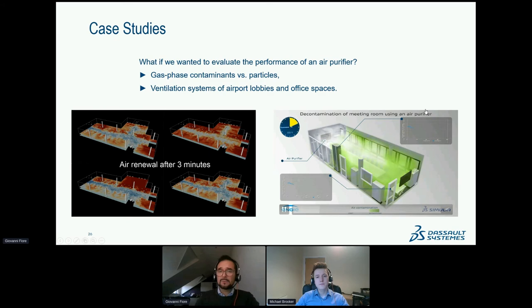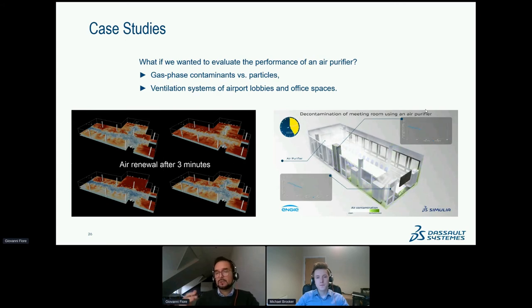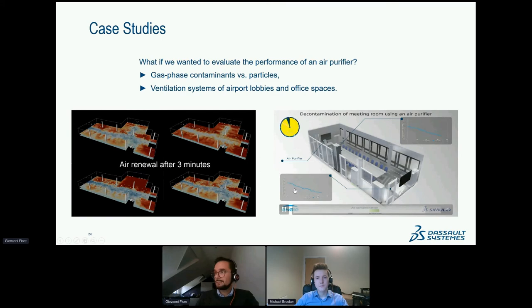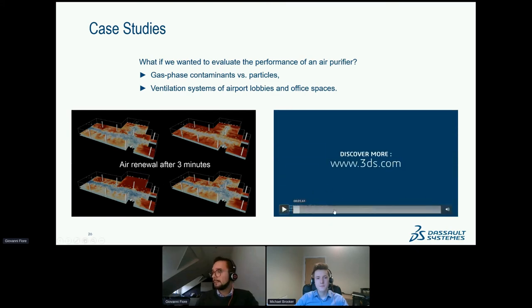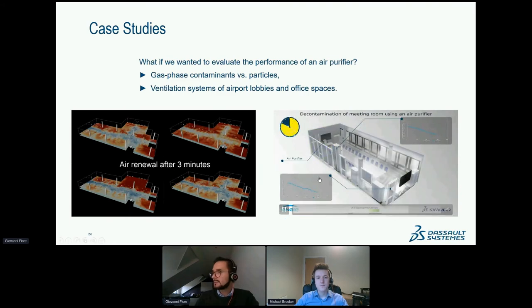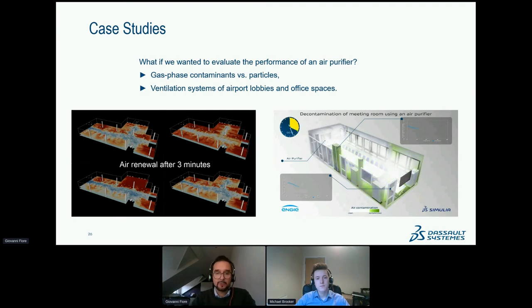For a smaller office space, we engaged with a company in Germany and monitored contaminant concentration over time with a purifier acting alone — no HVAC system — as a worst-case scenario. The purifier took approximately 50 to 55 minutes to flush all the contaminant out of the room. The decaying trend was clearly visible in the graphs and animation, demonstrating how effectively — or not — a purifier solution can clean the air.